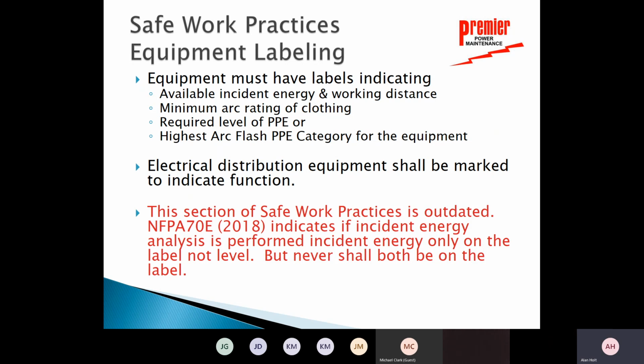So here's a section that's a little outdated, but I just want you to be aware of it. We talked earlier about all the pieces of electrical equipment shall be labeled. And not only just labeled, but there are some specific parts to this that are pretty good. It says that equipment must be labeled, including available incident energy and working distance, minimum arc flash rating of clothing, required level of PPE or highest arc flash PPE category for the equipment. Okay, so they've kind of got some strange wording in here, but basically they're labels.